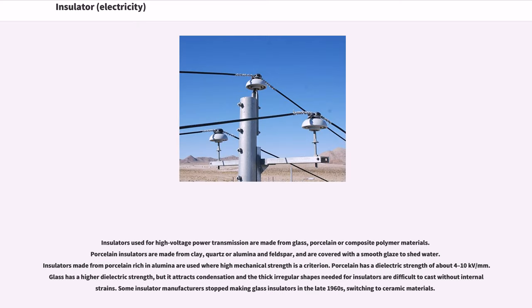Insulators used for high-voltage power transmission are made from glass, porcelain, or composite polymer materials. Porcelain insulators are made from clay, quartz or alumina and feldspar, and are covered with a smooth glaze to shed water. Insulators made from porcelain rich in alumina are used where high mechanical strength is a criterion.